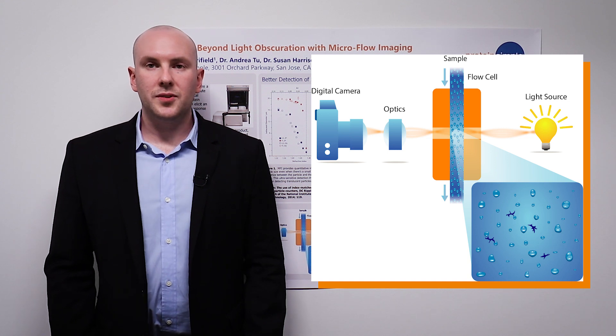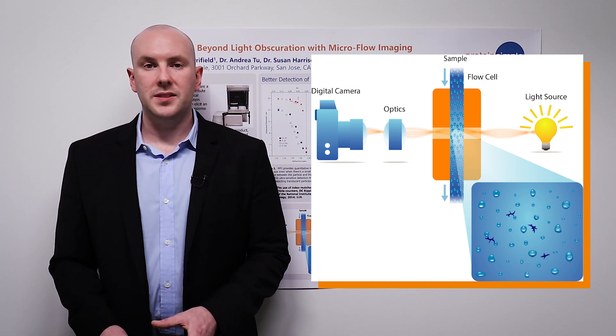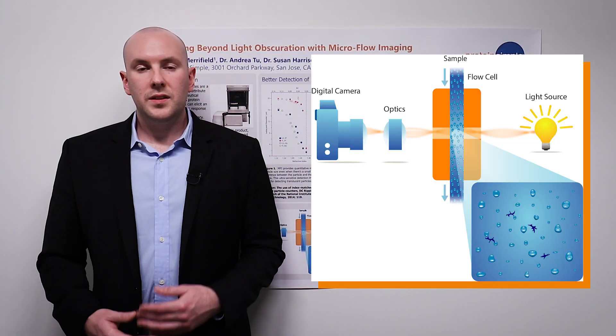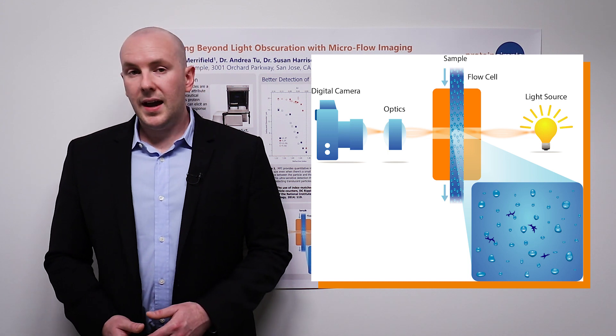In between that, we have the flow cell, and the flow cell is crucial for guiding the path of the sample past the optics. This provides two essential things. First, it makes sure that we image as much of the sample as possible — MFI is able to image up to 85% of the sample that is passed through. This is very important for ensuring that the results are statistically significant, and if you're doing something like final product QC, you're able to analyze the vast majority of the sample recovered from that specific vial or syringe.